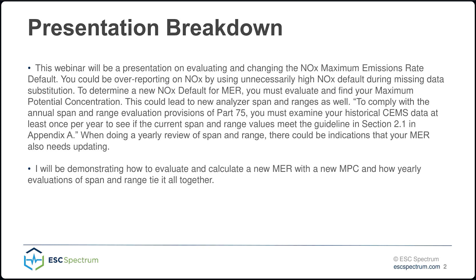This is a presentation on evaluating and changing the NOx maximum emissions rate default. Why that's important: you could be overreporting on NOx by using unnecessarily high defaults during missing data substitution. I recently did a project for a customer and realized I didn't necessarily know the correct way to do it based on the monitoring plan instructions. The correct way to determine your NOx default for MER, you must evaluate and find a new MPC — maximum potential concentration. What this could then lead to are new span and ranges, so there are a few different things that go into this. You can't just find the new MER and say, okay, this is my new default. It's a little more involved than that.